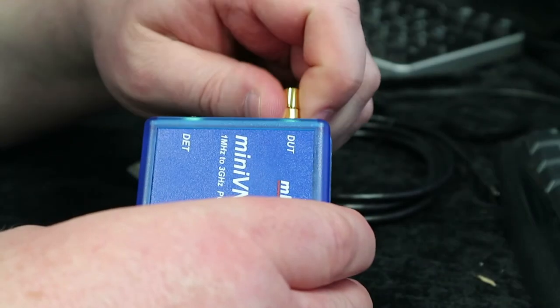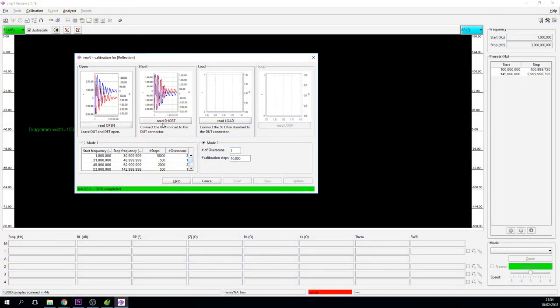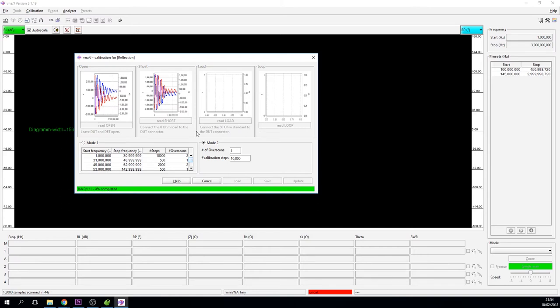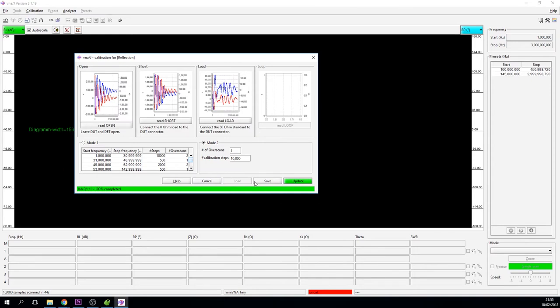Okay, that's the next one done. The next one I'm going to need is a load. Again we've got a little funny little Christmas tree. Now this one may look a little different because it's a load and we're going to say read it. Again it should only take about 30 or so seconds. When we're done with this we're going to ask to save the calibration because we're running this file independently, we're not actually installing anything. So it will keep asking to calibrate this every time you use it and we don't want to keep doing that, it's really dull. What we're going to do is save it and once this is done, there you go, pretty much done.